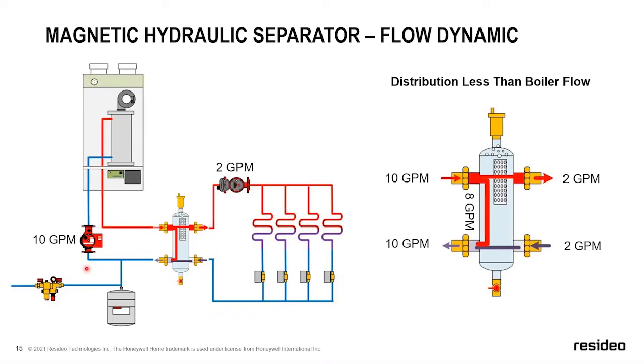So what you have is, again, I'm going to use that 10 gallon a minute example here. This is still the same flow rate that we've got, but now let's say we're using zone valves with a variable speed pump. That variable speed pump is going to fluctuate the flow rate based on the number of zone valves that are open. So in this example, let's just say hypothetically, we've got one valve open. This pump is seeing the pressure there, so it's going to drive 2 gallons a minute. This pump still must maintain that 10 gallons a minute maximum flow rate to provide adequate flow.